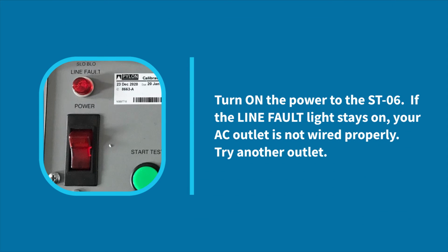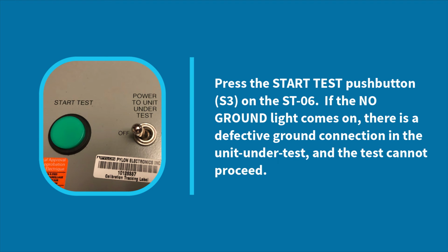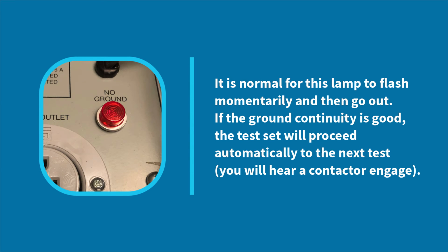Turn on the power to the ST06. If the line fault light stays on, your AC outlet is not wired properly. Try another outlet. Press the Start Test push button S3 on the ST06. If the no ground light comes on, there is a defective ground connection in the unit under test, and the test cannot proceed. It is normal for this lamp to flash momentarily and then go out. If the ground continuity is good, the test set will proceed automatically to the next test. You will hear a contactor engage.